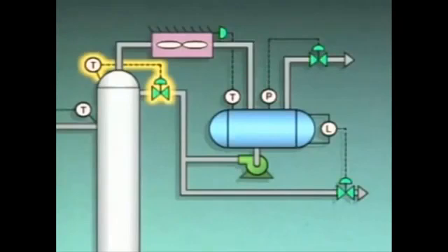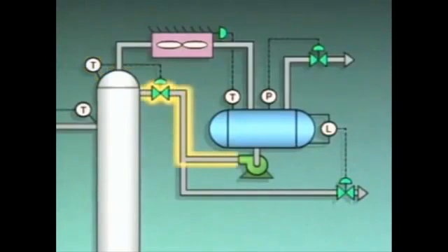When the external reflux control loop senses a decrease in the temperature, it decreases the flow of reflux to the tower. In some distillation systems, the external reflux flow is kept constant. The amount of condensation is varied by changing the temperature of the reflux. Introducing cooler reflux into the tower has the same effect on product composition as increasing the flow of reflux to the tower. In this topic, we looked at how a tower's control system responds to changes in bottom temperature. We also looked at how product composition can be affected by changes in external reflux.